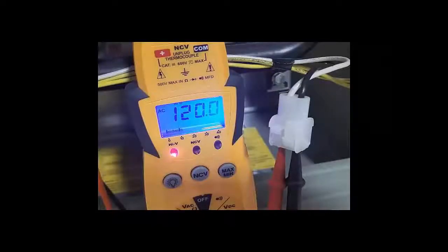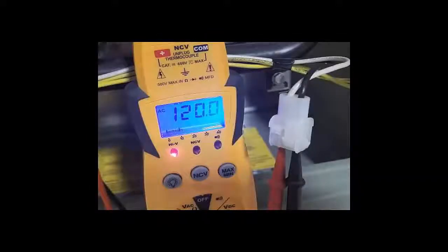This can easily be done by unhooking the Molex plug with the wires leading to the igniter and connecting a voltmeter to the wires going back to the circuit board. Now again, make certain the main power is off while you're doing this. Once your meter is connected to the wires, simply turn the main power back to the unit on. Within 30 seconds or so, you should get a reading of 110 to 120 volts.